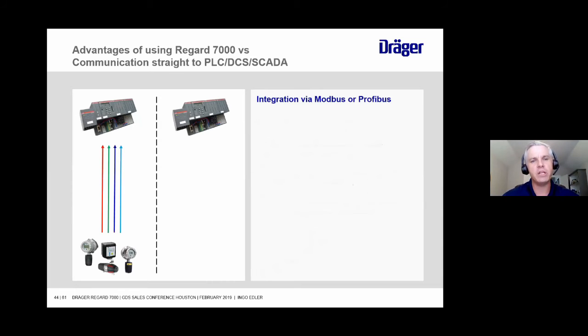So these are our different transmitters that we'll be talking straight to a PLC or DCS. Like I mentioned, there's issues. If you wanted to add an additional point, you'd have to make sure you have enough room, make sure you have a 4-20 input card on that DCS or that PLC, and you have to go and program that new input in the future. It's going to be very costly and time consuming.